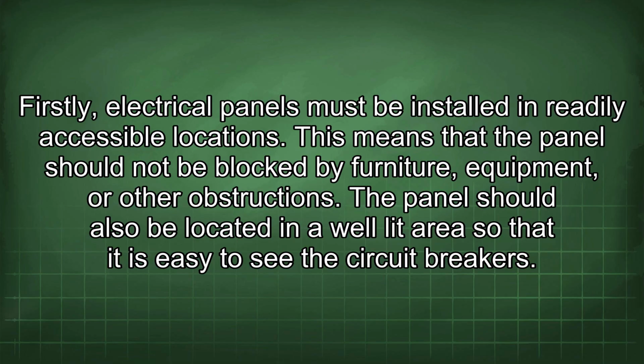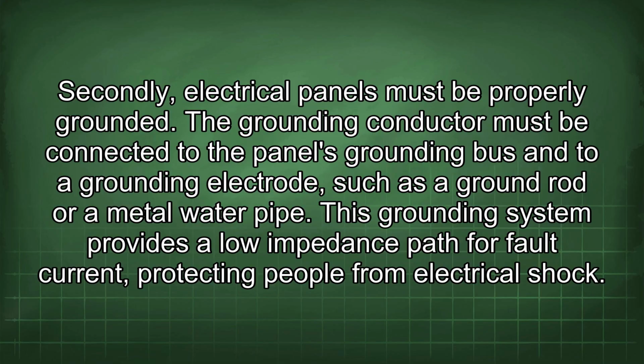Firstly, electrical panels must be installed in readily accessible locations. This means that the panel should not be blocked by furniture, equipment, or other obstructions. The panel should also be located in a well-lit area so that it is easy to see the circuit breakers. Secondly, electrical panels must be properly grounded. The grounding conductor must be connected to the panel's grounding bus and to a grounding electrode, such as a ground rod or a metal water pipe. This grounding system provides a low impedance path for fault current, protecting people from electrical shock.